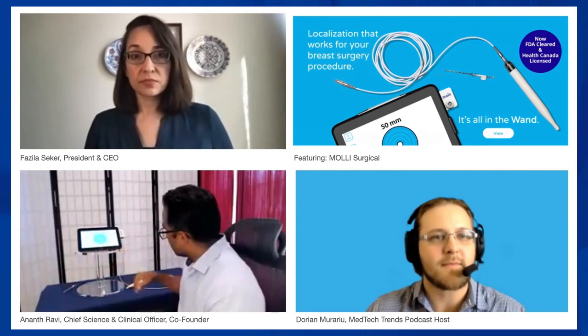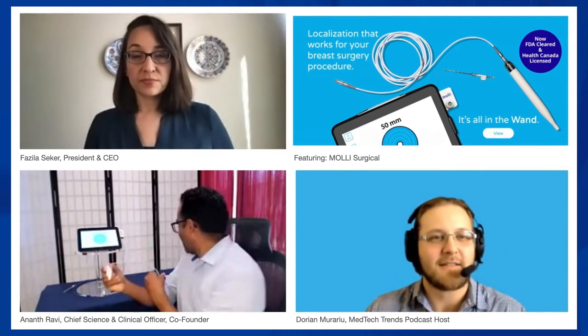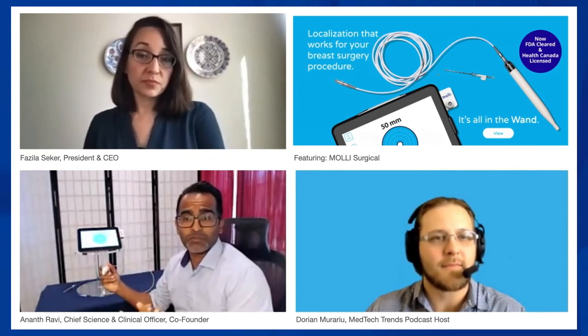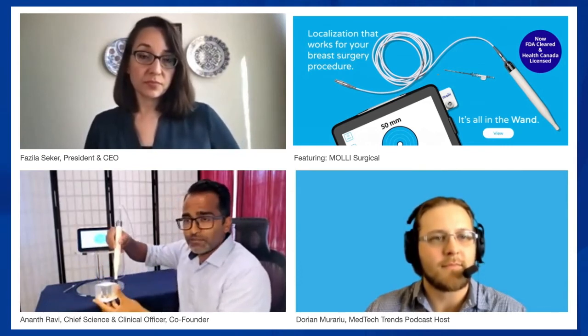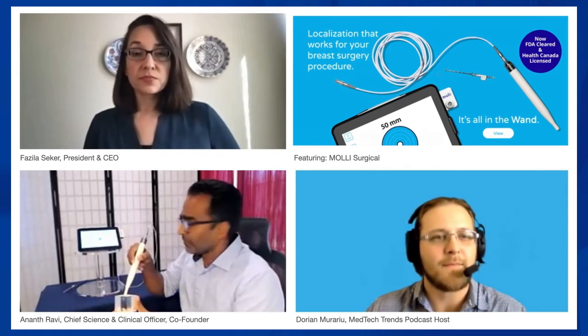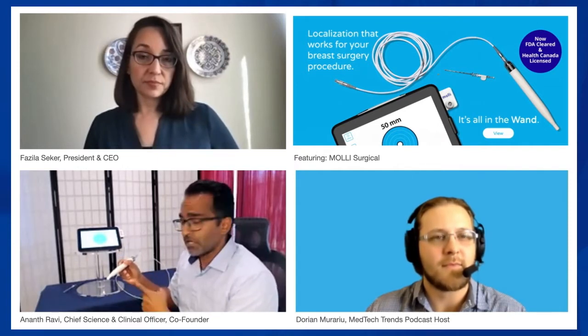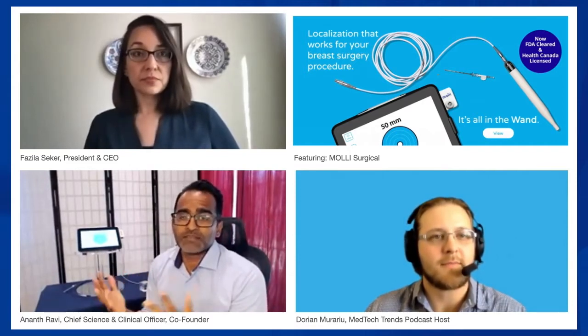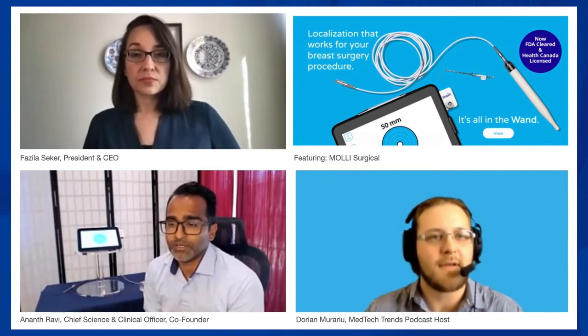On top of that, we created a tablet and a wand — we call it a wand because, tongue-in-cheek, the magic is in the wand. The tablet and wand were created with the surgeon in mind for ease of use. There are three modes of feedback: the surgeon uses the wand like a GPS. They place it on the surface of the breast, and there's audio feedback, graphical feedback, and a distance readout in millimeters — measuring the distance from the marker to the tip of the wand. The overall system is designed to give that care team confidence without complexity.